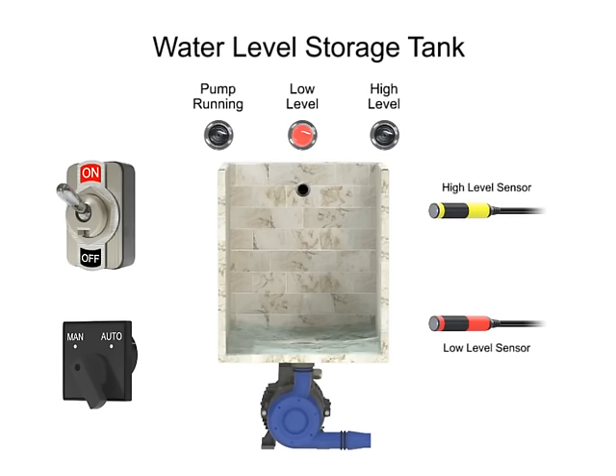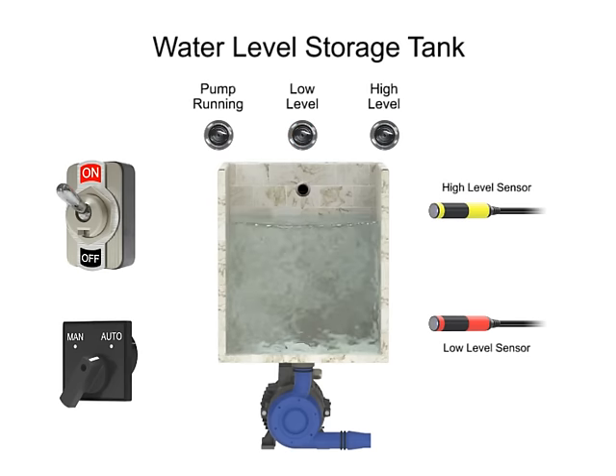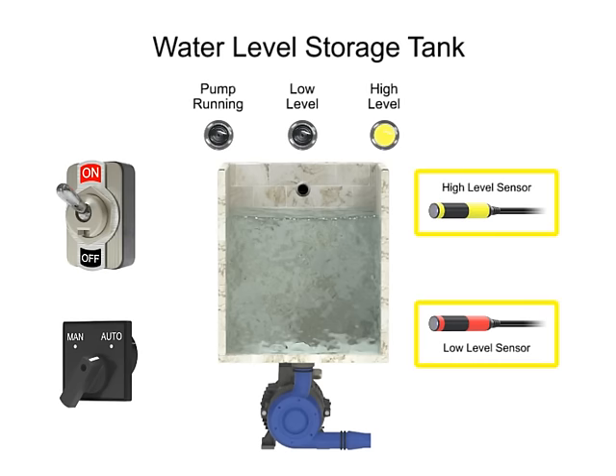The Automatic mode of operation is selected by turning the switch to Auto. The program will control the discharge pump motor automatically by monitoring the high and low sensor switch inputs.